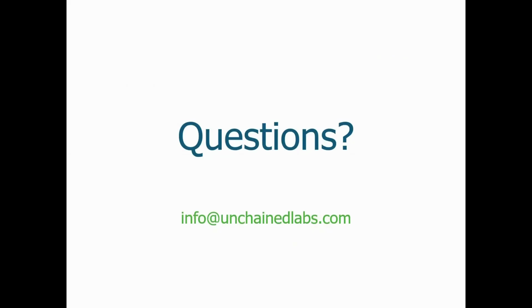Our first question is from Caroline, and this came earlier before you mentioned SYPRO orange. She asked, were the results you were showing with or without SYPRO orange? Thank you very much for this question. I saw it coming in, so I am assuming it was based on the monoclonal antibody work, and that one was done focusing solely on the protein intrinsic fluorescence. If the protein has plenty of fluorescence by itself, then that's our preferred way of analyzing it. Only if there is a condition where there is no protein intrinsic fluorescence would we resort to the extrinsic fluorescence. Or, for example, if you have an older protocol that you want to carry over, use SYPRO orange. But the monoclonal antibody work in the first case study was done without any SYPRO orange present.